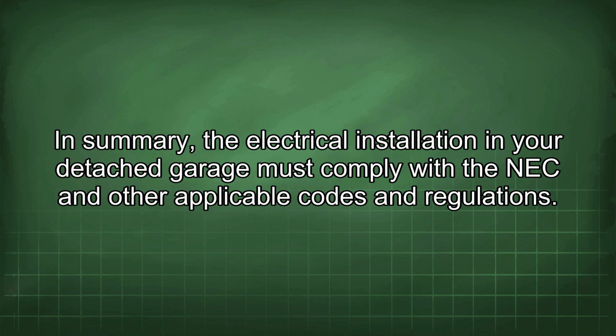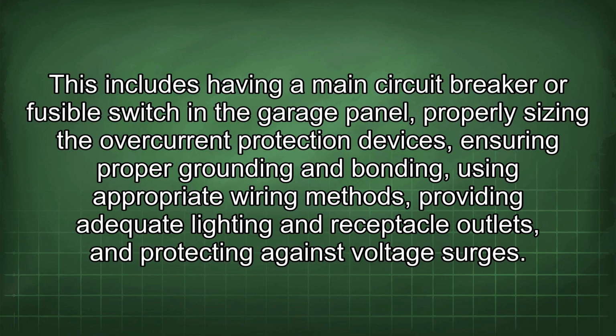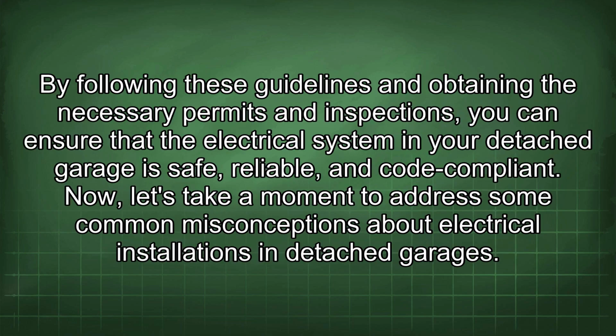In summary, the electrical installation in your detached garage must comply with the NEC and other applicable codes and regulations. This includes having a main circuit breaker or fusible switch in the garage panel, properly sizing the overcurrent protection devices, ensuring proper grounding and bonding, using appropriate wiring methods, providing adequate lighting and receptacle outlets, and protecting against voltage surges. By following these guidelines and obtaining the necessary permits and inspections, you can ensure that the electrical system in your detached garage is safe, reliable, and code compliant.